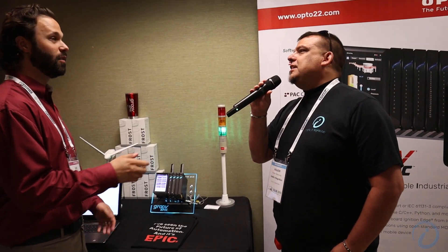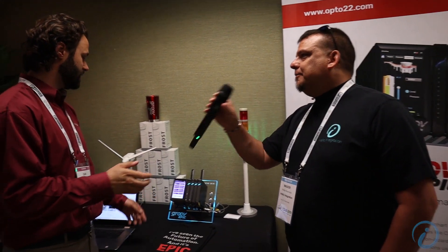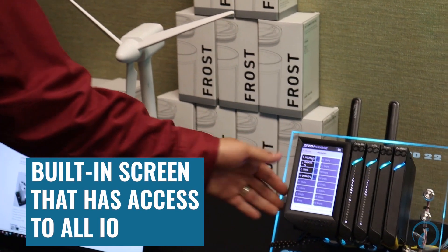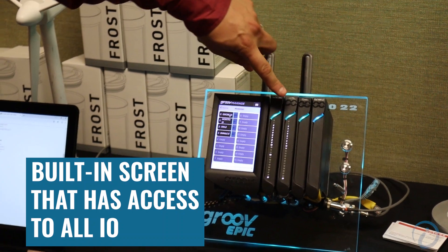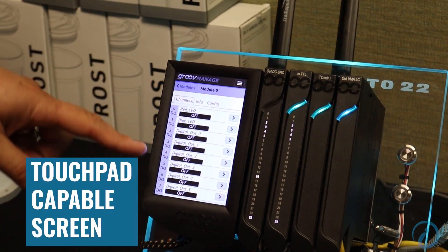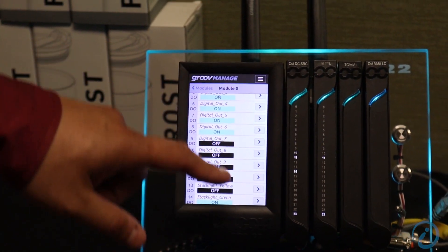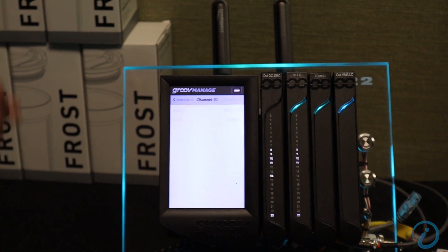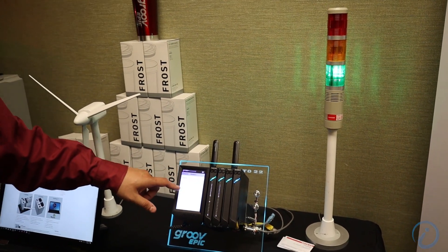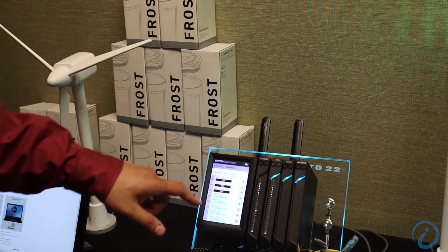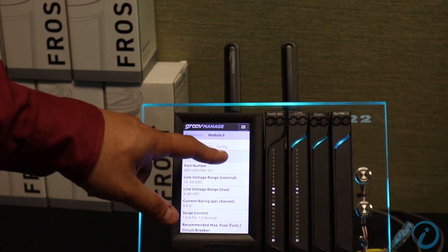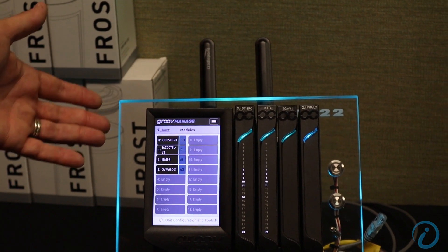What's the use case for the screen on the EPIC? There are lots of things. We have a built-in screen which has access to all of the IO. The IO modules themselves have touch pads, so you can touch an IO module and it'll bring you directly into the IO channels, where you can toggle points on and off for troubleshooting and testing. You also get information on the IO modules including wiring diagrams, module specifications, and details.